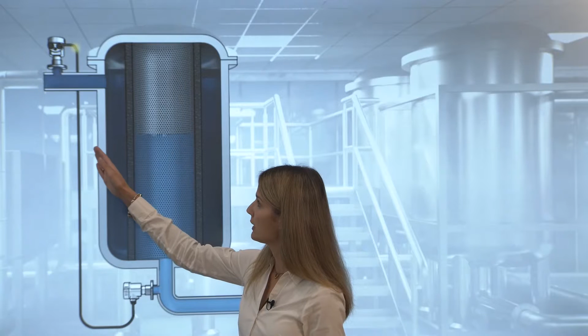Another method to separate the different cells and microorganisms is via a filter system, as you can see here in the back. Here we also have to monitor the filter for any kind of buildup, for example, to plan any cleaning process of the filter. So the monitoring of the filter is also done in that case via an electronic differential pressure. So we have a sensor installed before the filter and one sensor installed behind the filter. Together they are combined with a cable, and they are then an electronic differential pressure system. This means as soon as the pressure rises, you know as an operator that the filter is blocked, that there's buildup, and it has to be cleaned.